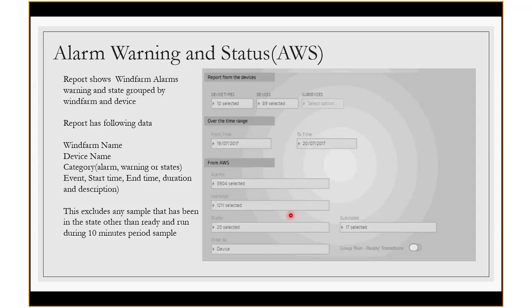This sequence of alarm is very important, since this is not a periodic interval kind of thing. Whenever there is an alarm, it gets pushed to the SCADA server, and the SCADA server stores the data on change of state. So until there is a change, it won't store the data, because this is AWS data. If it's 10-minute data, then it stores the data periodically - we'll see that in the next slide.